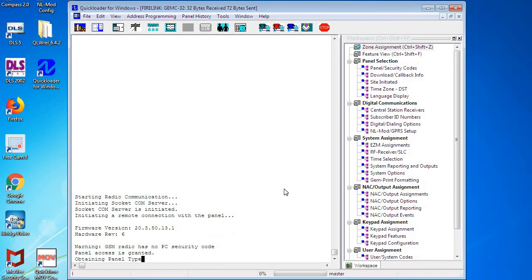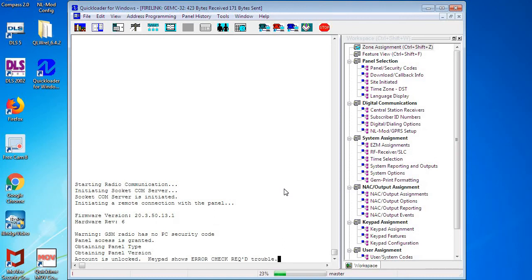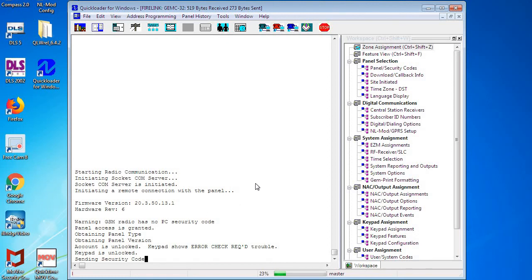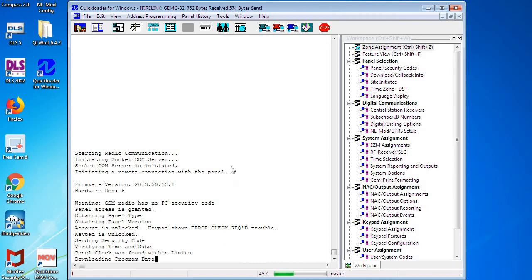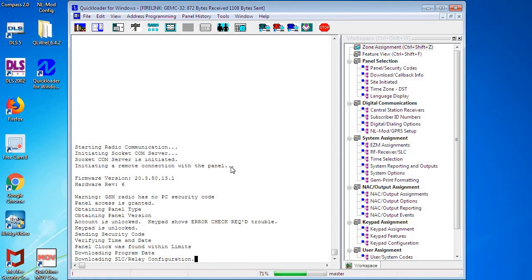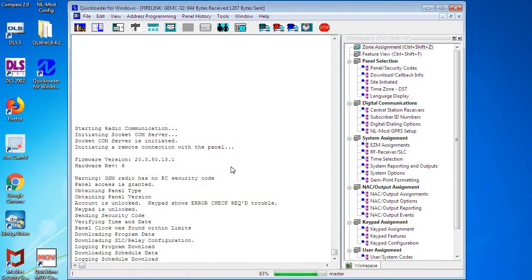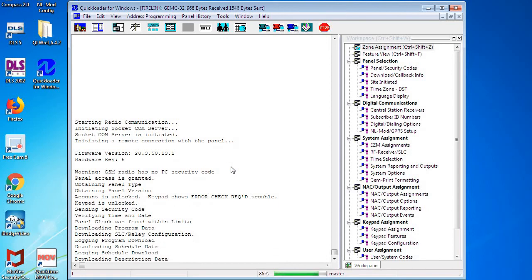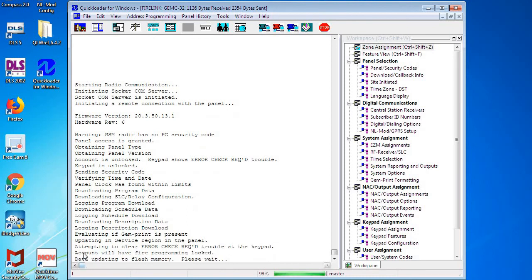And again, you need to make sure that your program is error-free. If there are errors in the program, there will be a prompt before you send a download telling you to correct the errors and display what errors, programming errors, you may have incurred. And coming up here shortly, because we did have an error-free program, we'll see that now Quick Loader is going to automatically attempt to clear the error check from the panel.